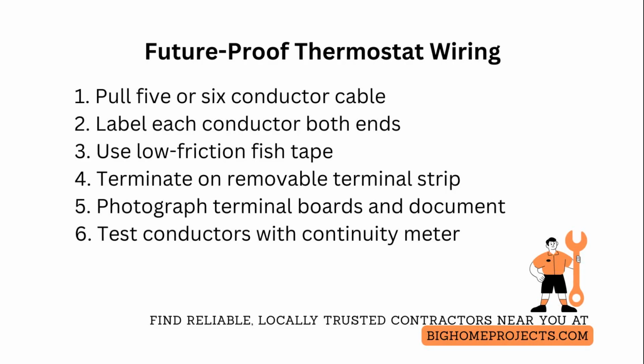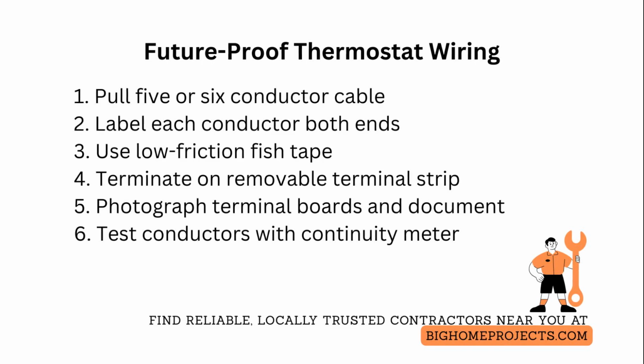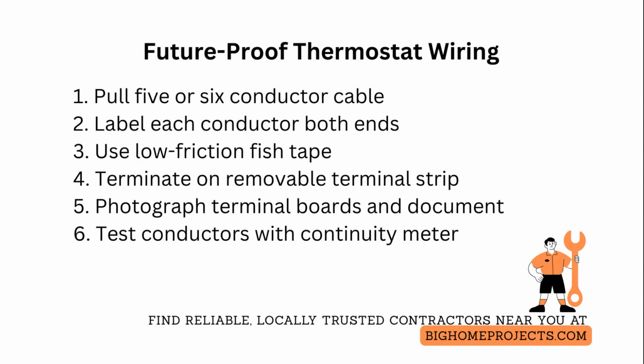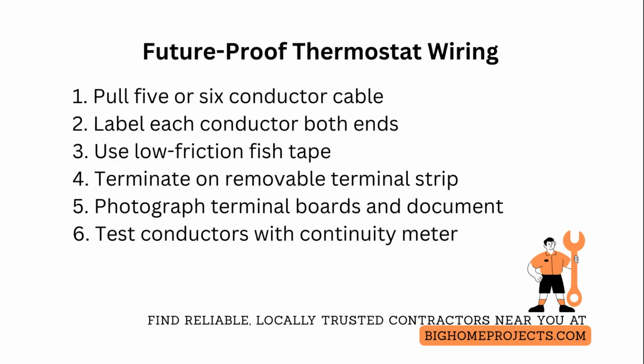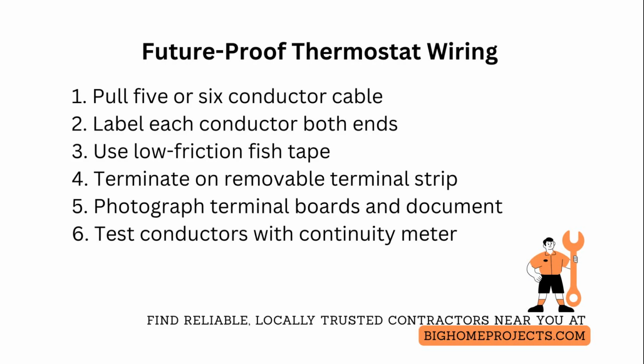If the system has a common contact missing for power-hungry smart thermostats, plan for a dedicated 24-volt transformer or use a powered common adapter, only as a last resort because it can mask deeper wiring errors. For multi-stage heat or cool and heat pump systems, document which conductor controls each stage and photograph terminal boards. Store the photos with the service record.